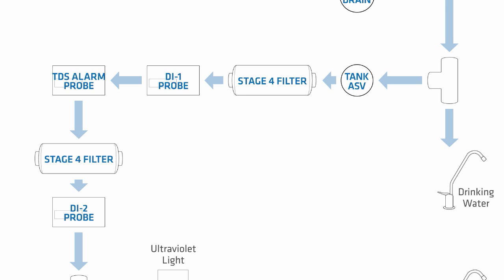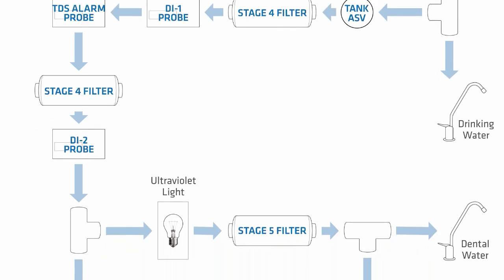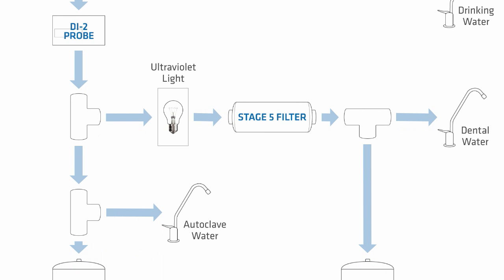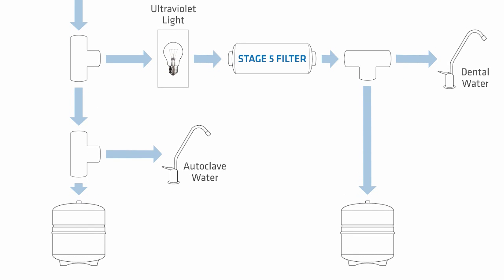From there, the water flows through the DI1 probe to read water hardness and then through the TDS alarm probe. Water then flows through the second Stage 4 deionization filter and into the DI2 probe. At this point, the TDS should be 0 parts per million. Then, the water flows into a second T connection, with one side going to the reserve tank with the autoclave water out, and the other side continuing through the ultraviolet lamp to irradiate viruses, bacteria, algae, and yeast. Finally, the water passes through the Stage 5 microbiological cartridge to treat the water with Sterisil's patented residual disinfectant, and then to the dental water output and reserve tank.